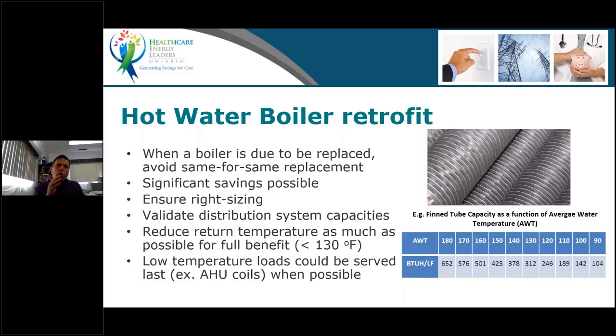Right size your boiler and pick the right combination of boilers. You may want a mix of condensing and high efficiency but non-condensing boilers, depending on your application and how the system was designed. Just be very careful not to blindly buy condensing boilers because they're more efficient. The rest of the system is important.